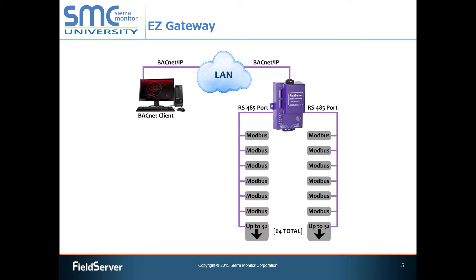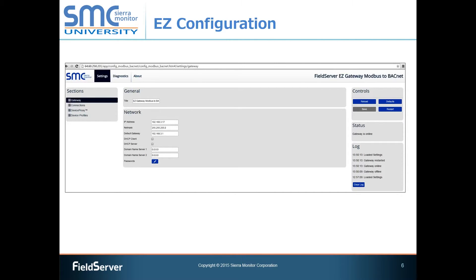Firstly, look to see if there's a field server easy gateway solution for your application. The easy gateway series offers package solutions for common applications and requires little configuration since a large portion of the application is pre-configured. Most site technicians familiar with communications would be perfectly comfortable configuring the easy gateway products themselves and would not need to allocate a large amount of time to do it. At the time of publishing this video, Sierra Monitor Corporation has easy gateway solutions for Modbus to BACnet and for KNX to BACnet. Please note that the software for these gateways is written only for applications where we have BACnet as a client. For example, the Modbus to BACnet easy gateway will represent Modbus devices in a BACnet network, but it is not capable of representing BACnet devices in a Modbus network. You will need the standard field server solution for that.